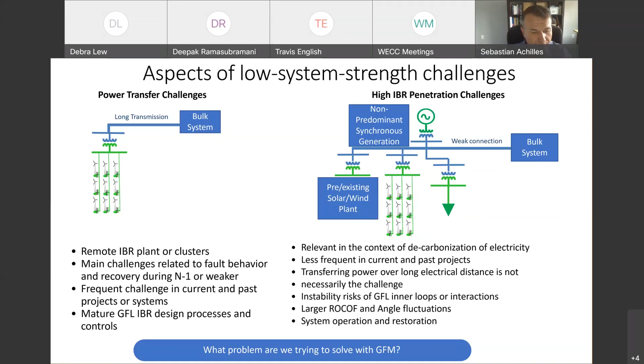In the interest of concentrating now on aspects of steady state, fault, and fault recovery performance issues, let's concentrate on those two. We can simplify the system on the left with a little cartoon similar to the systems Nick was elaborating, and for the same reasons Nick elaborated. You have that simple equivalent where you have a reactance—it represents the electrical distance from the point of interconnection of the wind plant to the stiff source—and then we have the inverter-based resource. From the point of view of power flow, the green arrow indicates that all the power coming out of the inverter-based resource is flowing through the reactance. That's why this is a power transfer challenge: we're trying to transfer a lot of power through a large reactance.